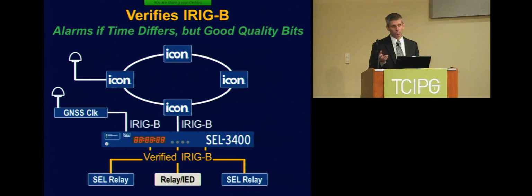At that point the device can do two things. One, it can decide not to trust anybody and go into holdover mode, sending out its own relative time to connected devices. Or two, it can force bad quality bits, relying on the end devices to recognize the time is no longer good, disregard it for critical applications, but keep using it for non-critical ones.